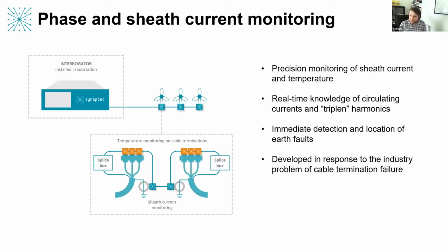First of all, one thing I wanted to mention before getting into the main power quality aspects: one of the interesting ways we can apply this remote monitoring solution is not for measuring the phase conductors, but for measuring the current that flows through the sheath, so the return path through earth in the cables. That could be the inter-array cables or the export cable to the onshore substation. For example, this opens up quite a lot of interesting possibilities.